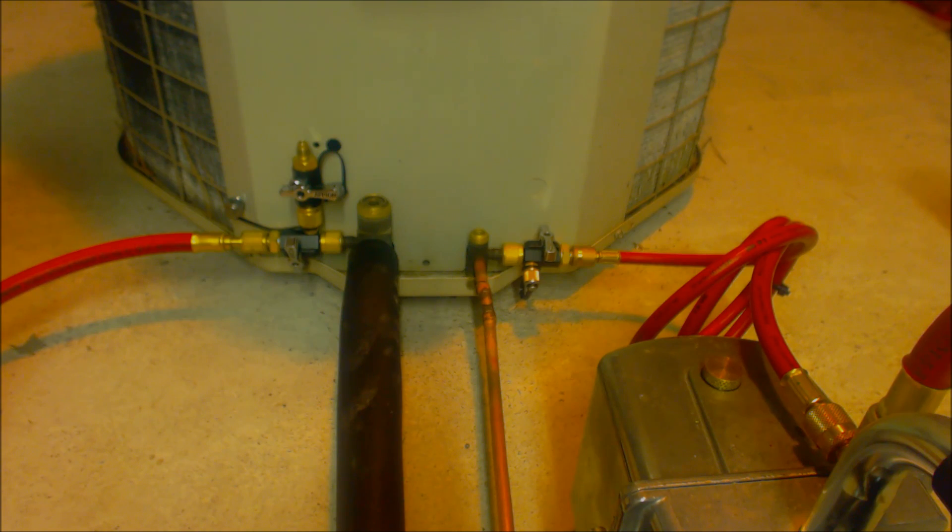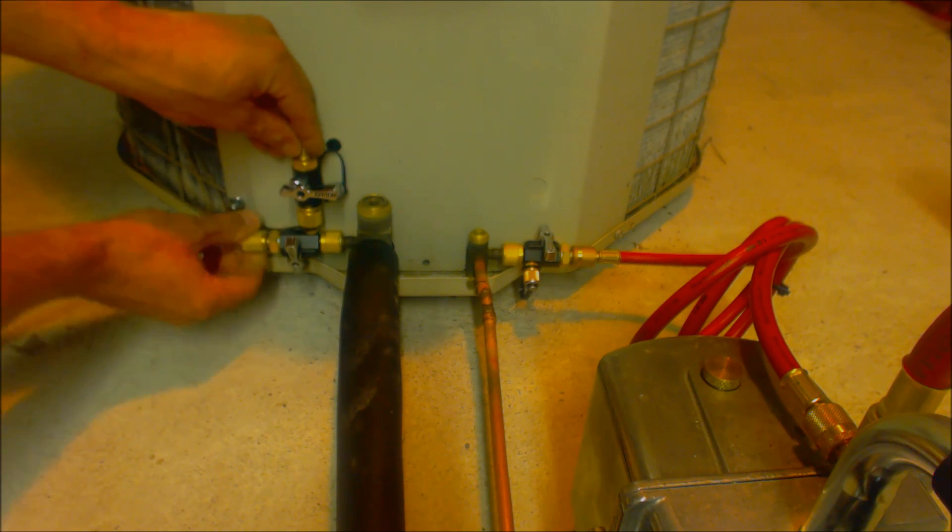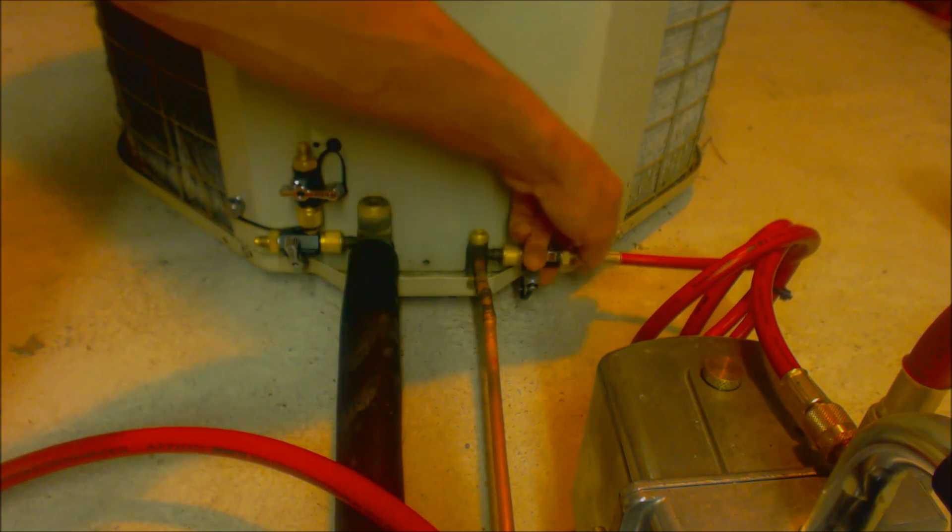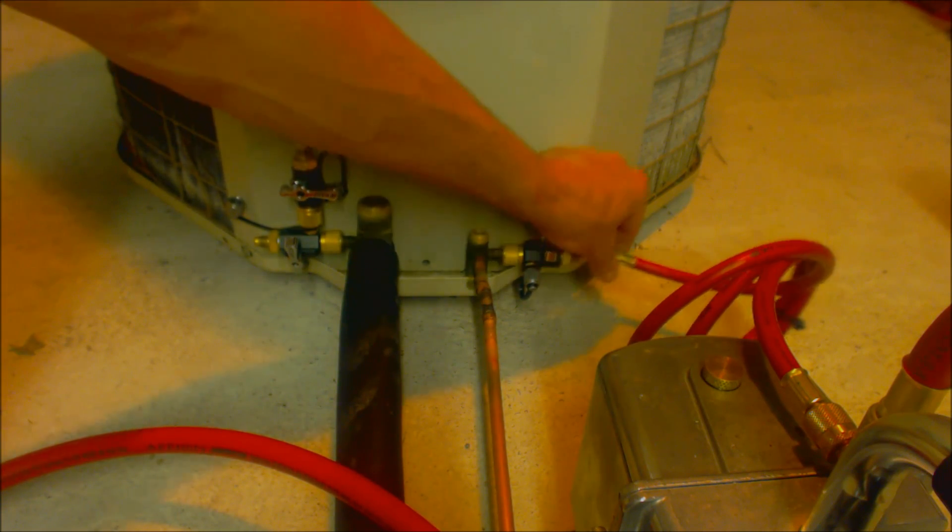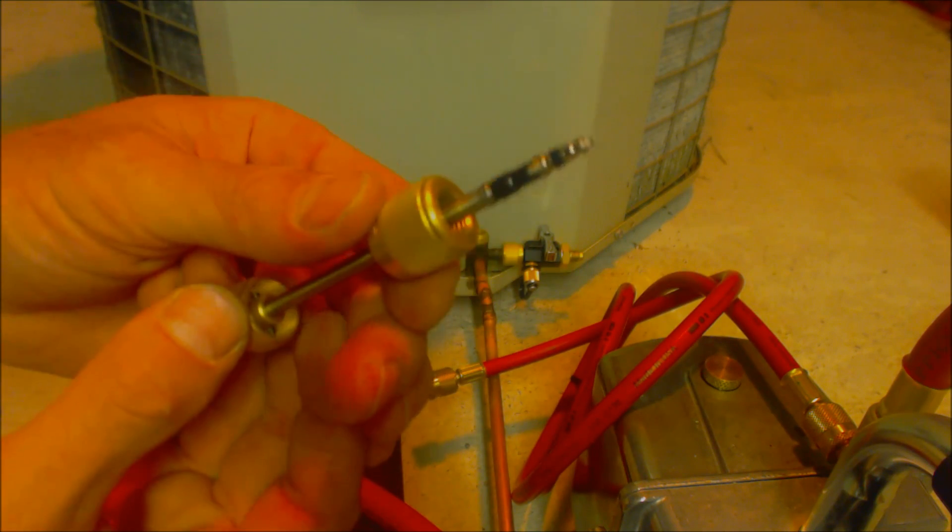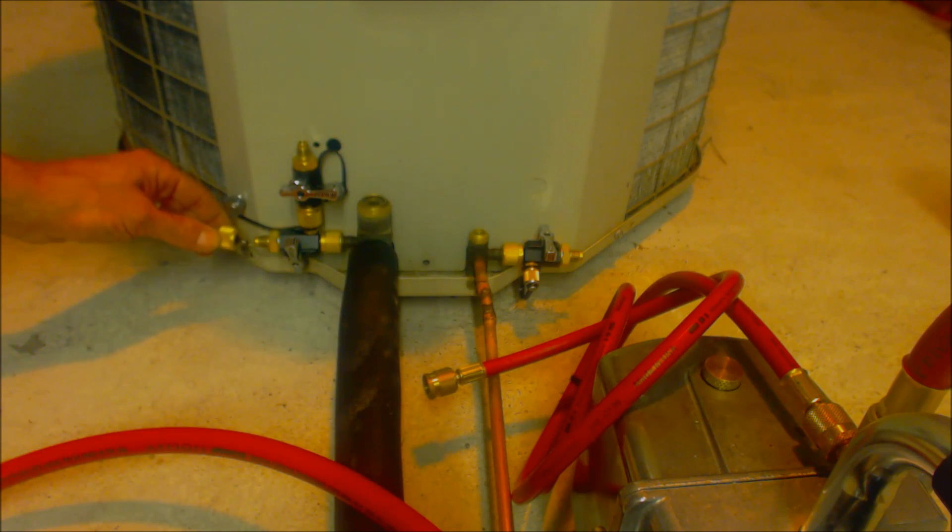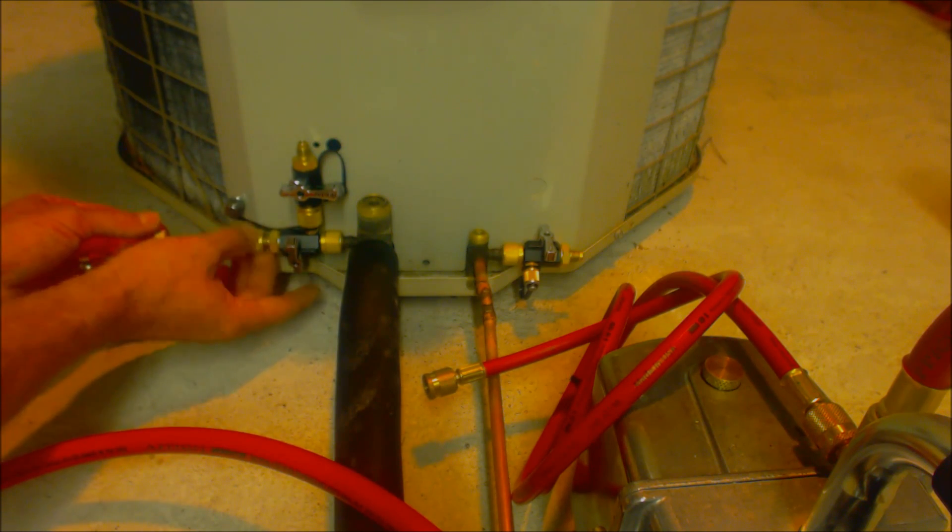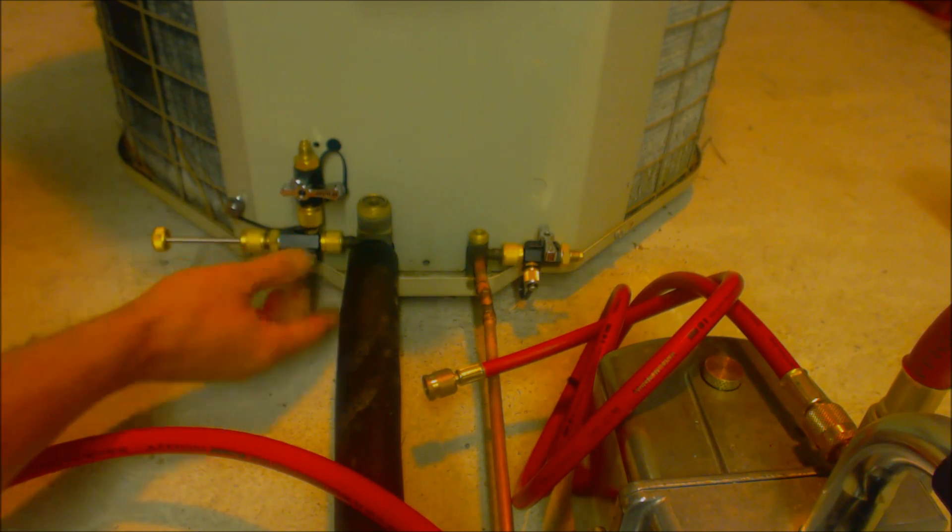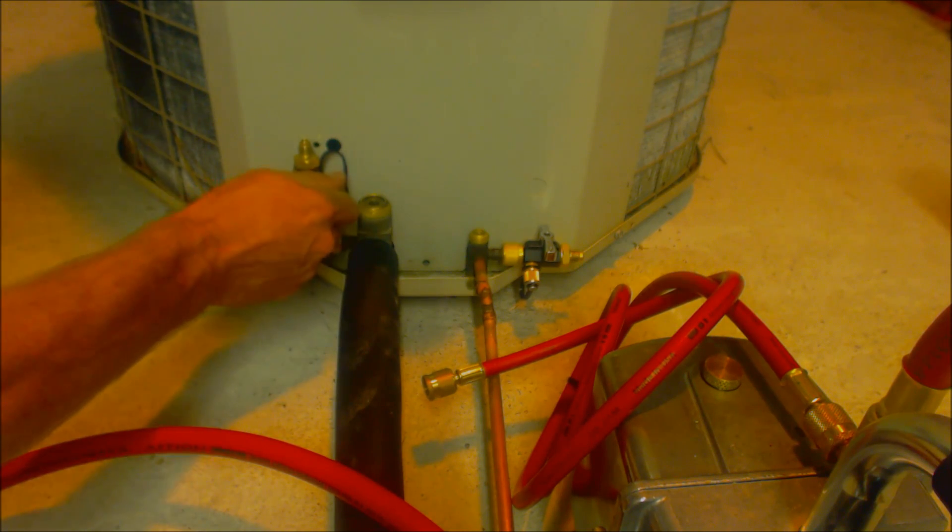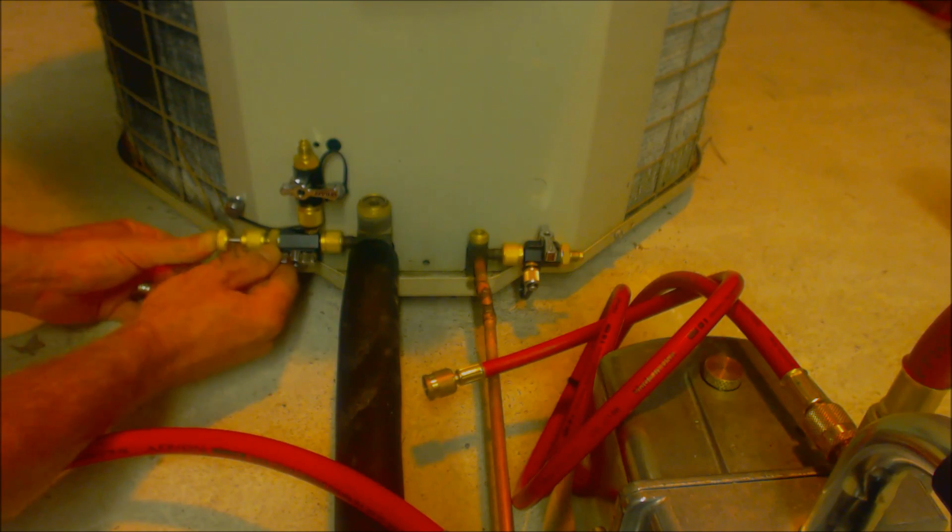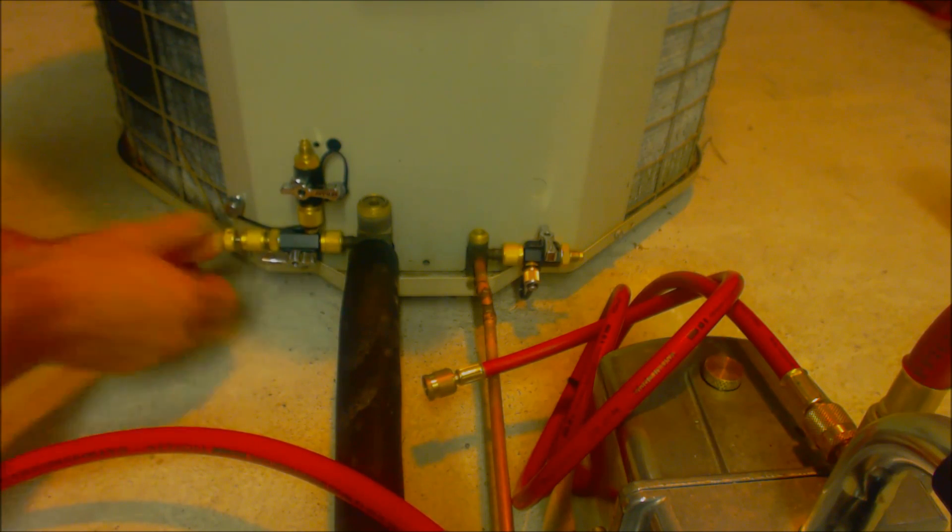What you do is you make sure that you have this nut up all the way to the front, and you go ahead and put it in. You can go ahead and open that up, and that's going to allow the pressure to come through. I'm going to purge any air out in the very back of this. Then we're going to put pressure this way while turning clockwise in order to screw the valve core back in.